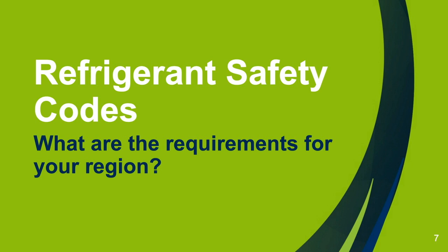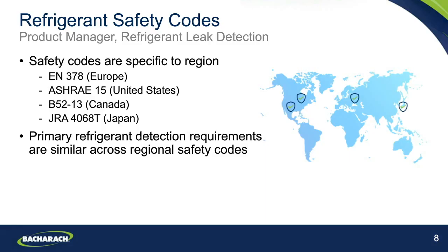So we'll push ahead and actually look at what the requirements are within the refrigerant safety codes. Now the standards vary and are specific to each region. Some specific ones to highlight are EN 378 in Europe, ASHRAE 15 within the US, B52-13 standards in Canada, and the Japanese Refrigeration Association 4068T standards in Japan. Now, of course, there are a wider range of standards than these across the globe, but this is just to highlight that there are those standards out there regionally. But what we do tend to see is that the requirements surrounding refrigerant detection tend to be broadly similar across the different regions. And what we'll focus in on today are in particular ASHRAE 15 and EN 378.